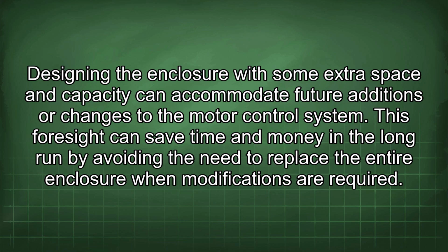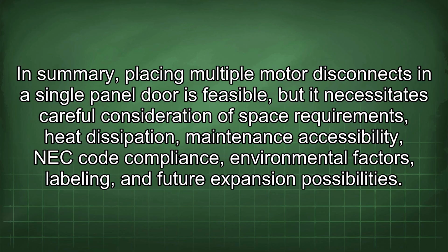Designing the enclosure with some extra space and capacity can accommodate future additions or changes to the motor control system. This foresight can save time and money in the long run by avoiding the need to replace the entire enclosure when modifications are required. In summary, placing multiple motor disconnects in a single panel door is feasible, but it necessitates careful consideration of space requirements, heat dissipation, maintenance, accessibility, NEC code compliance, environmental factors, labeling, and future expansion possibilities.